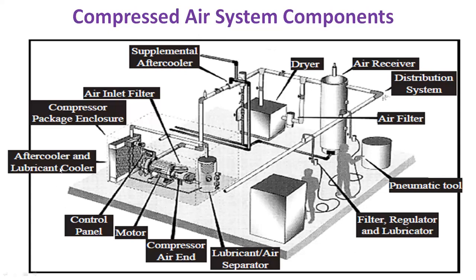After coolers are used to remove moisture, and air dryers remove residual moisture in the pipeline. Moisture drain traps — including manual drain cocks and time-based or automatic drain valves — are used at pipe section ends to remove moisture. Air receivers provide storage and smooth the pulsating air output, reducing pressure variations. Each component needs to be well maintained for overall good network performance.